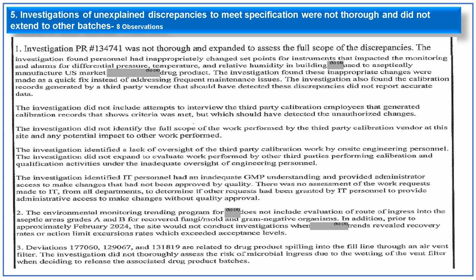The fifth 483 observation is that investigations of unexplained discrepancies were not extended to other batches. There are 8 sub-observations under this fifth 483. The first one is that the investigation was not thorough and not expanded to assess the full scope. There was an investigation where it was found that persons had inappropriately changed the set points to underestimate the alarms for differential pressure, temperature and relative humidity in the building for the aseptic manufacturing facility.